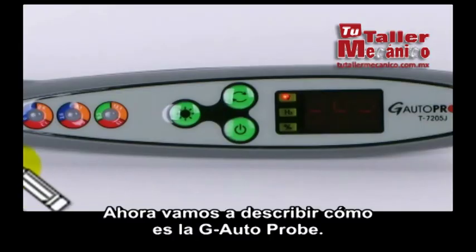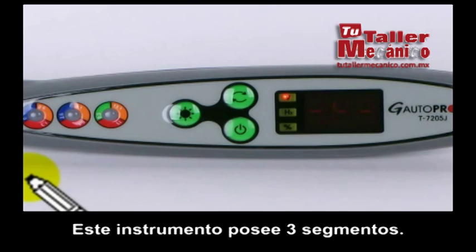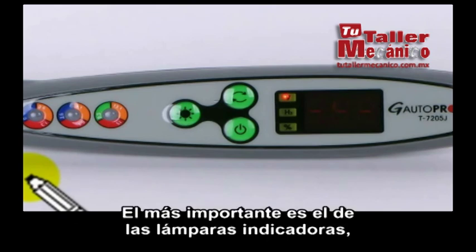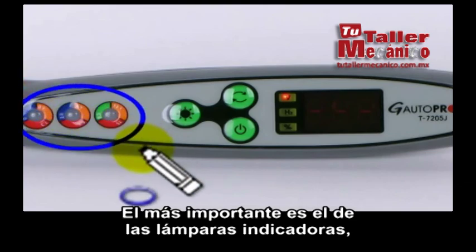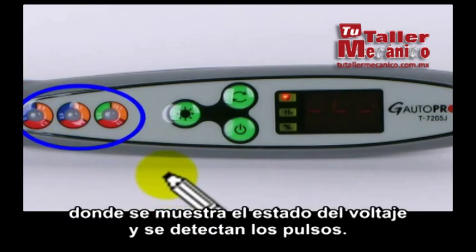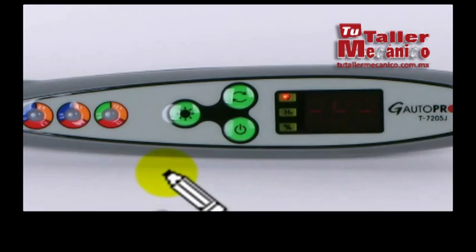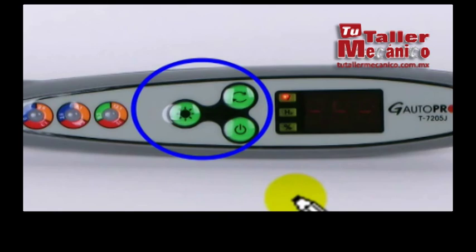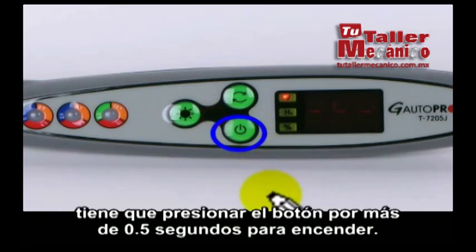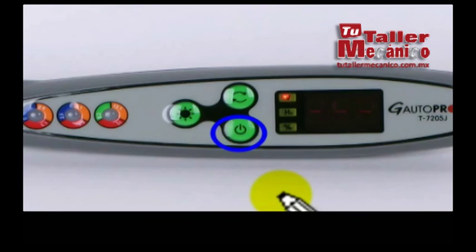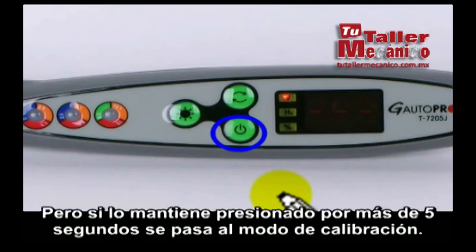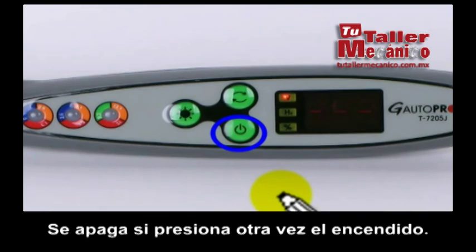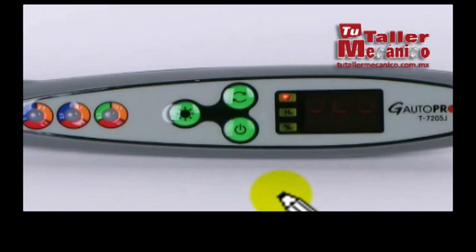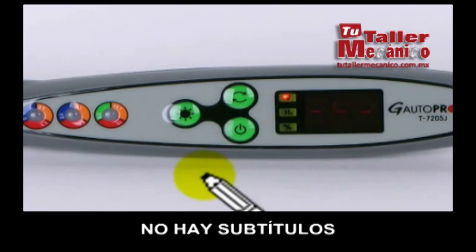Let me explain the composition of G-Auto Probe now. G-Auto Probe is broadly segmented into 3 parts. The most important part is the LED lamp indicator. It shows the state of voltage and the pulse measured. The next one is the switch part. This is power. Push the button for more than 0.5 seconds to turn on. If you keep pushing the button for more than 5 seconds, it enters calibration mode. It turns off if you push the power again. It turns off after 3 minutes when it is not used, to save the battery.